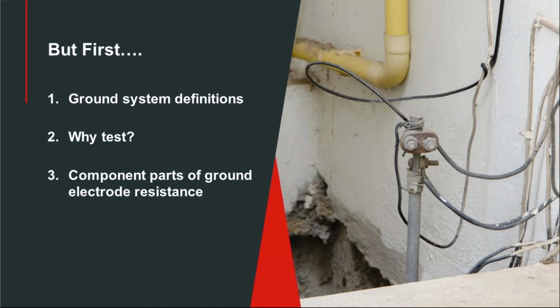That's how you go about establishing that you've met your ground. There are two ways this is commonly done. One is drive and test: you drive your rods deeper, or add more rods, and keep testing until you get the number you want on your resistance. There's nothing wrong with that, and it's commonly done. The drawback is the increments become smaller and smaller, so the testing can become tedious after a point.